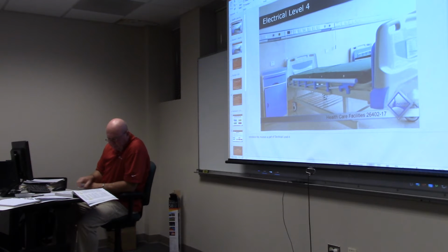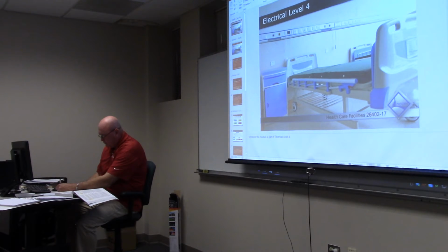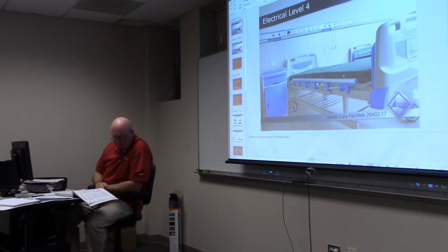In facilities that do not require type 1 or type 2 EES, emergency power may be provided by batteries in accordance with 700.12. 700.12. Okay. And we'll take a look at that. That's on page 6 is where we found that, under other healthcare facilities. Okay. All right. Number 9.